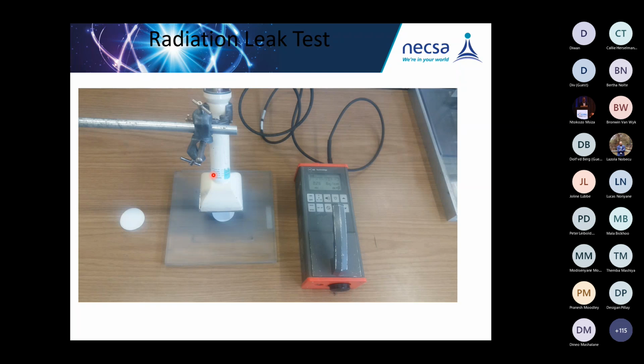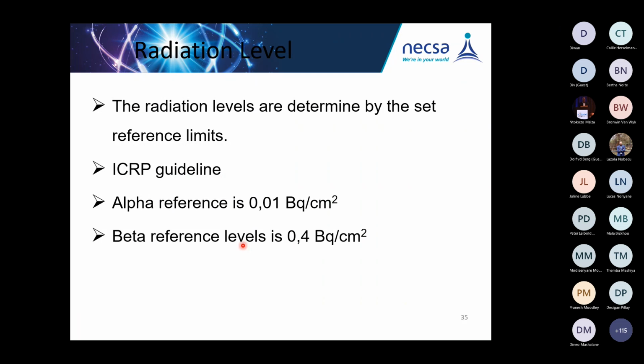I've lifted these probes higher so that you can see nicely the paper, actually the one that you perform the leak test. It is at the center of the probe. And then the radiation levels are determined by the ICRP guidelines. For alpha, that is 0.01 becquerel per square centimeter, and for beta it is 0.4 becquerel per square centimeter.